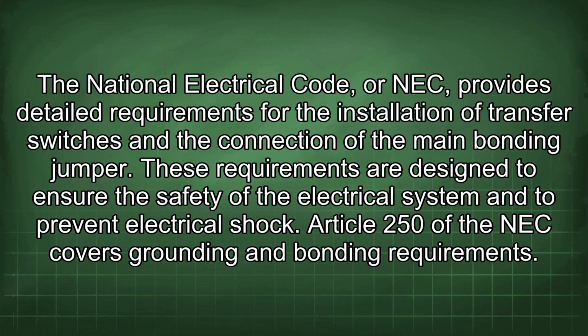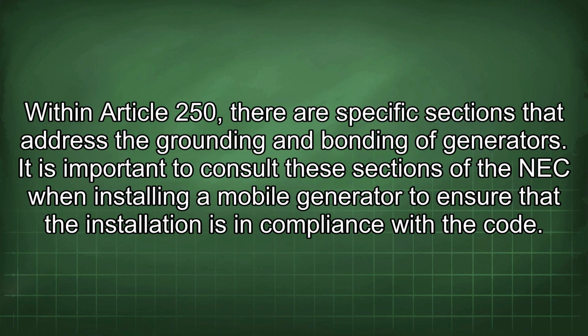The National Electrical Code, or NEC, provides detailed requirements for the installation of transfer switches and the connection of the main bonding jumper. These requirements are designed to ensure the safety of the electrical system and to prevent electrical shock. Article 250 of the NEC covers grounding and bonding requirements. Within Article 250, there are specific sections that address the grounding and bonding of generators. It is important to consult these sections of the NEC when installing a mobile generator to ensure that the installation is in compliance with the code.